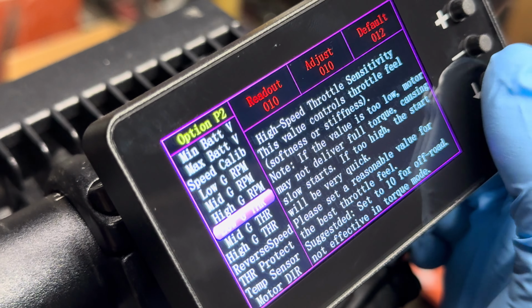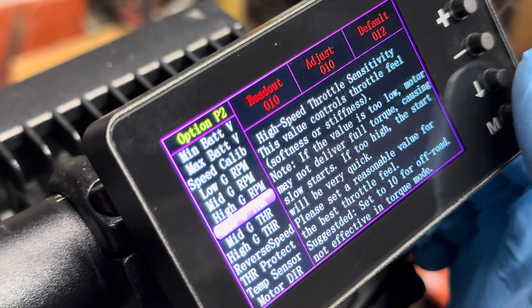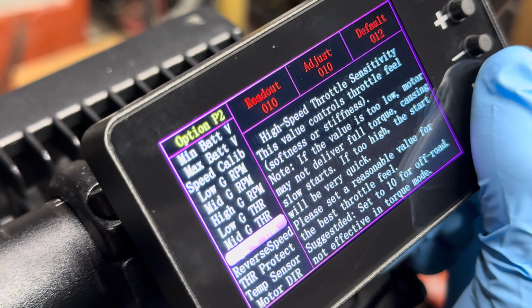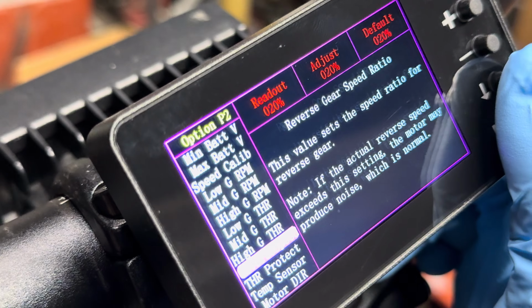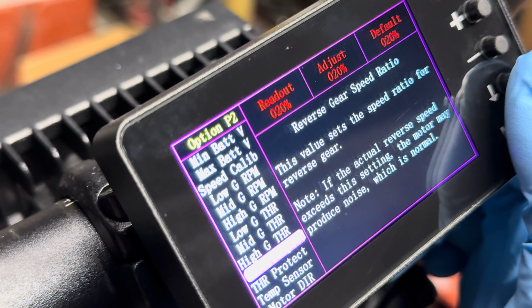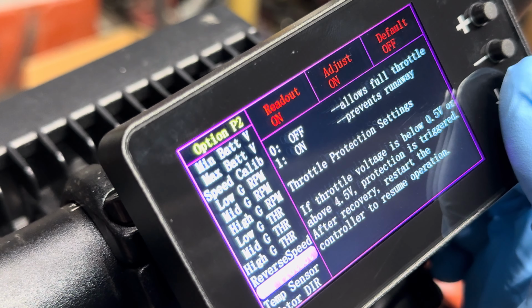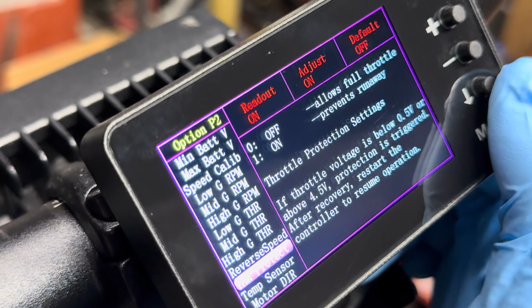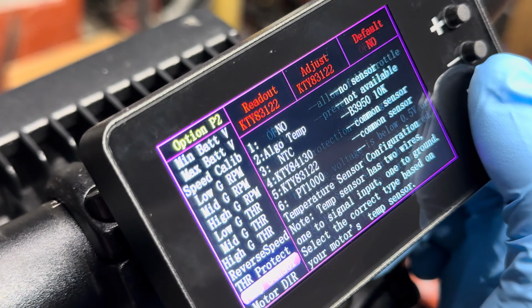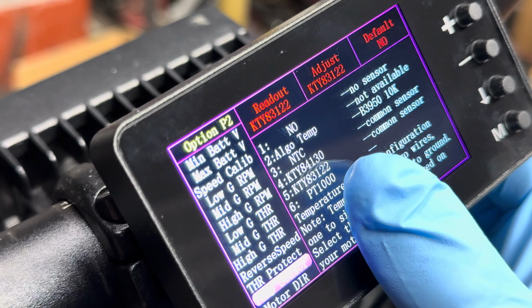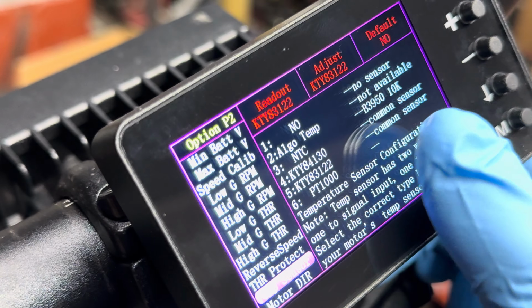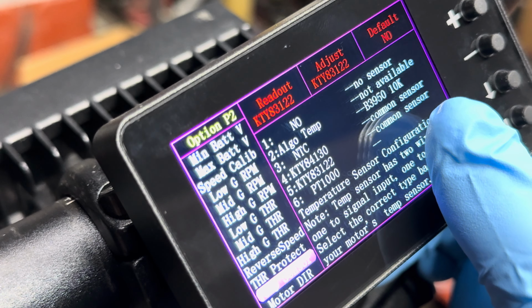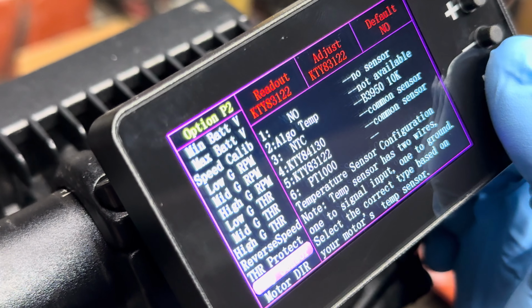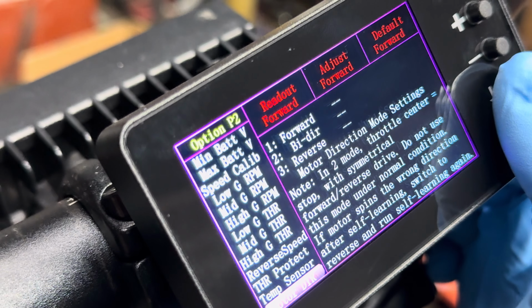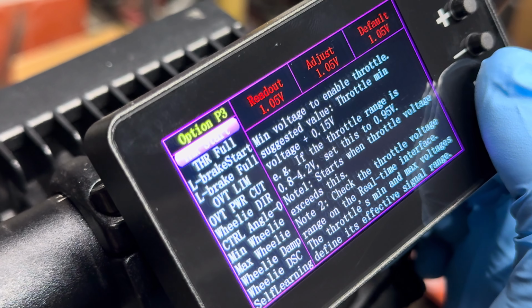This is throttle sensitivity. It comes at 12. I like 10 better, so I set it to 10 for all the modes. Reverse speed, 20%. You really don't need to be going any faster in reverse than that. Throttle protect on. This protects you from runaway throttles. Temp sensor in this motor for the E-Ride 2.0 is the KTY 83122. So we have that set and reads correctly. Our motor direction is forward.